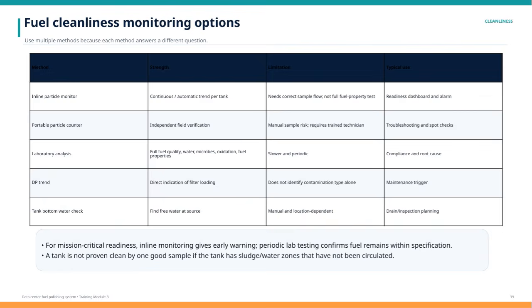Inline particle monitors provide continuous, automatic trending for each tank. This is great for real-time readiness dashboards and alarms, but they require correct sample flow and don't give a full picture of fuel properties. Portable particle counters are excellent for independent field verification. They're handy for troubleshooting and spot checks, although they involve manual sampling and need a trained technician to operate.